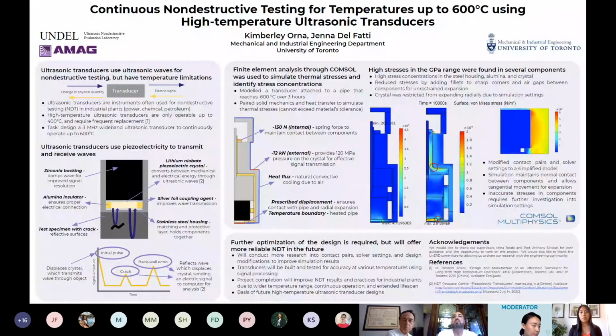Over the past summer, we've been working with AMAG, a company that supplies NDT devices to these industries. However, on the market right now, high temperature transducers are only operable up to 400 degrees Celsius and break down rather easily. Our goal was to design a 3 megahertz wideband ultrasonic transducer to continuously operate from room temperature up to 600 degrees Celsius. We also aimed to minimize all the internal stresses so we can extend its lifespan to up to 2 years.